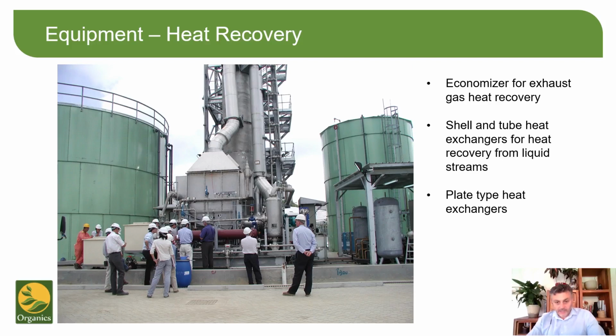Of course, material selection, manufacturer quality control, and design are of critical importance too. The temperatures we expect some of the equipment to work at is such that the incorrect material selection can lead to serious problems. The wastewaters we treat are dirty and corrosive and have a high solids content, so the heat exchangers must either accommodate this or be easily serviceable.